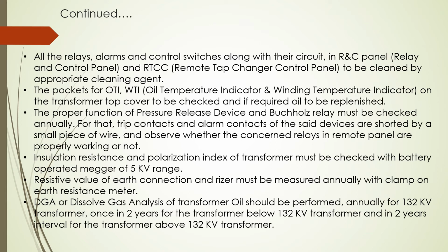All the relays, alarms and control switches along with their circuit in R&C panel, basically R&C is relay and control panel, and RTCC, remote tap changer control panel, to be cleaned by appropriate cleaning agent. The pockets for OTI, WTI, this is OTI is oil temperature indicator and WTI is winding temperature indicator, on the transformer top cover to be checked and if required oil is to be replenished.